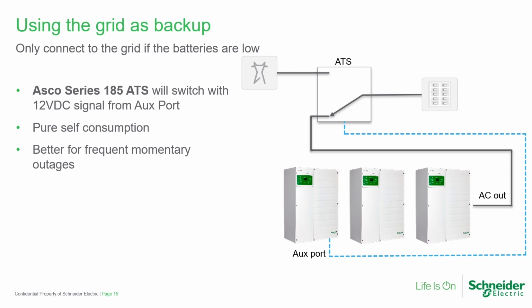Using the grid as backup can be used as an option for customers who live in areas where selling is prohibited. This can also be the purest form of self-consumption, and if the system is designed properly, connection to the grid will be seldom. Here you can see that the ATS is being driven by the aux port, and connection to the grid would only occur if the batteries get low.